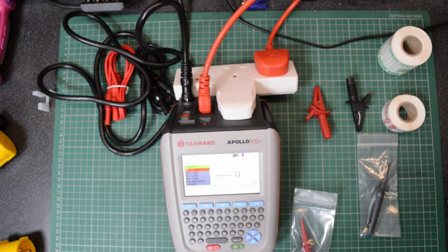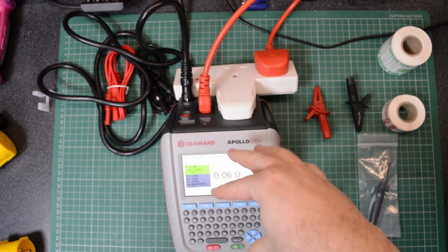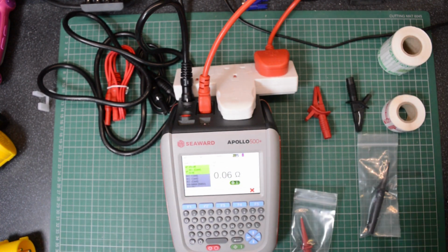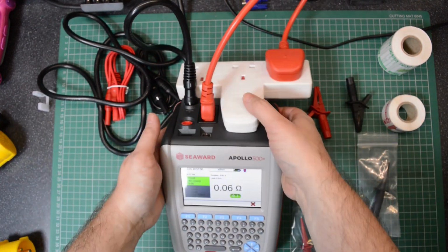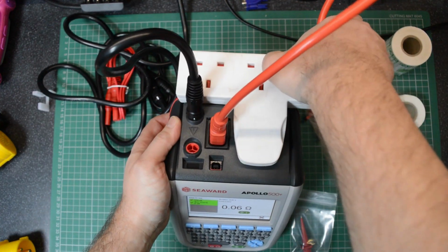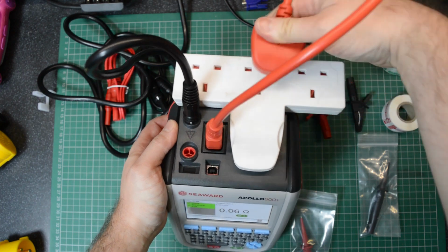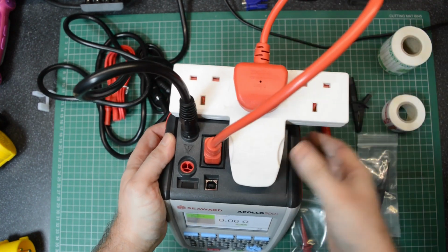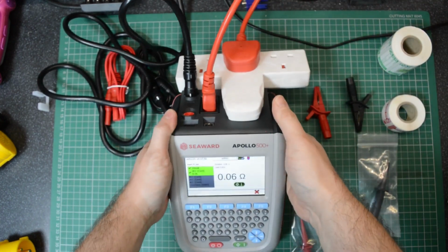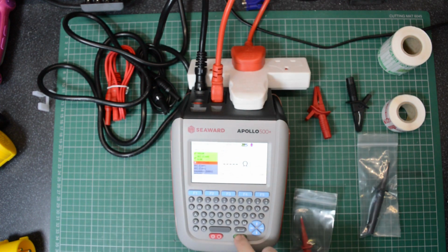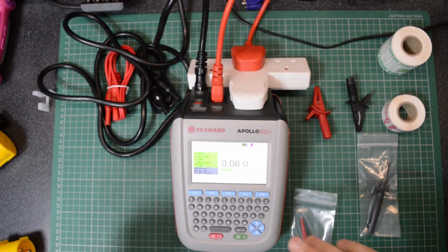It's now going to go ahead and do the continuity test. 0.06, so that's a pass. It now wants me to change the plug over because it knows it's a 4-way adapter. It's only a 3-way adapter here, but it thinks it's a 4-way adapter. So what you can do is set your own up. I can have a 3-way or 4-way or 6-way, for example. That's now going to test socket number 2. 0.08.